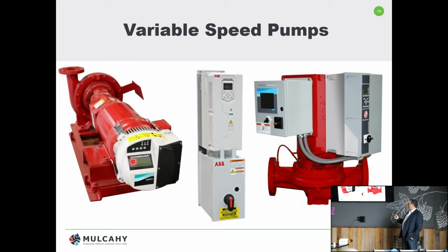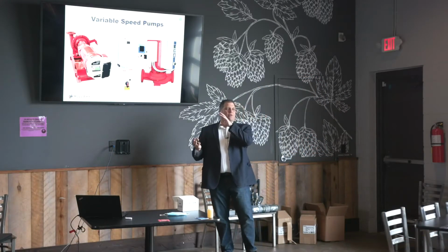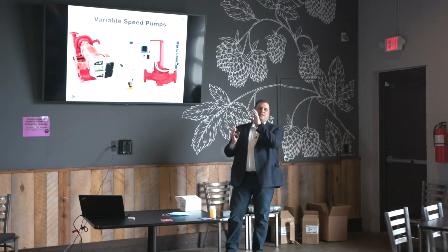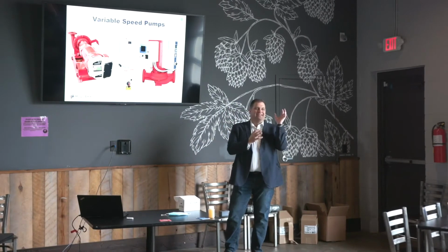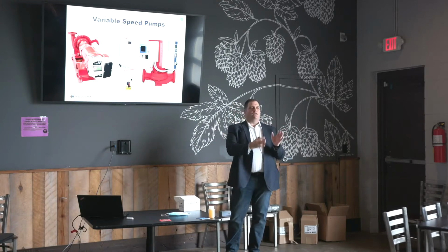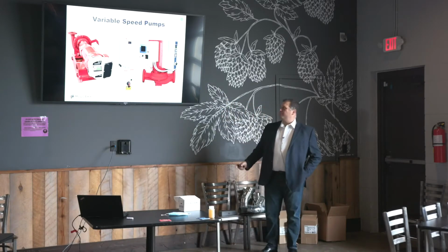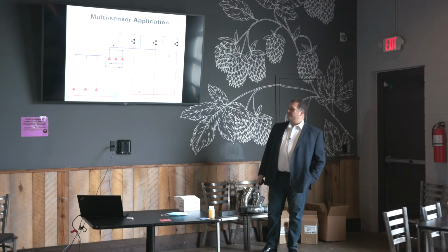So there are drive pump packages available. We can usually, and some drives, we can actually bolt them to the back of a TEFC motor and it uses the fan of the existing motor. Or we can go with the old-style ABB separate drive. Truth be told, our preference is for the separate drive because putting something that's electric that vibrates and is wet is setting yourself up. So if you have the space, let's hang the drive on the wall. And that goes a long way for the system operation. But we do have packaged drive and pump systems.